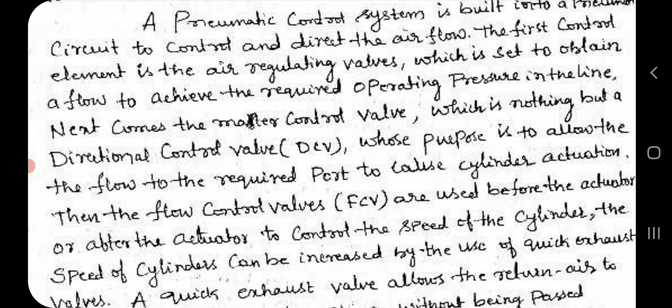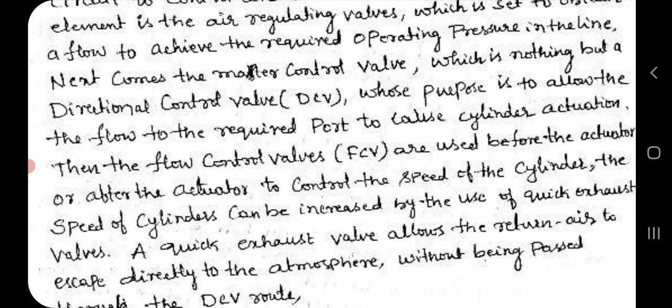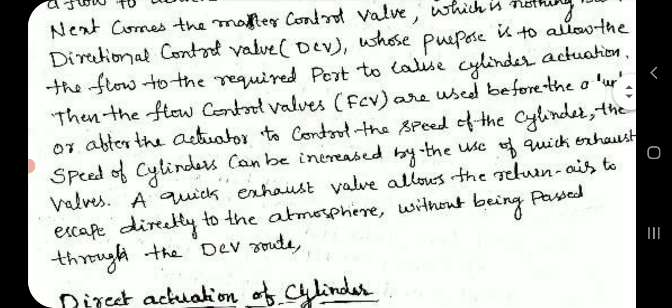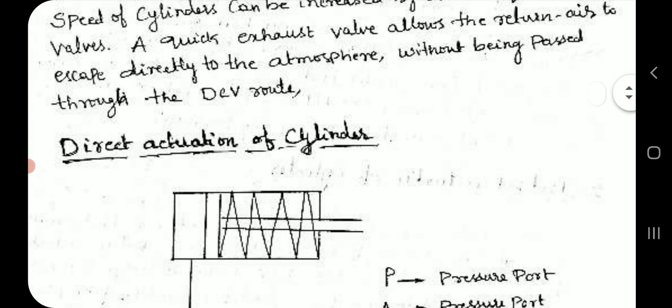Flow control valves are used before or after the actuator to control the speed of the cylinder. The speed of cylinders can be increased by the use of quick exhaust valves. A quick exhaust valve allows the return air to escape directly to the atmosphere without being passed through the directional control valve route.